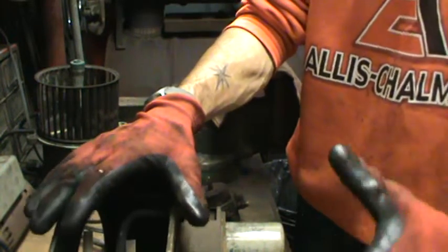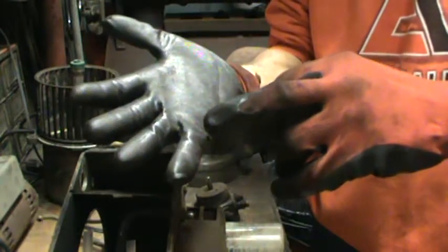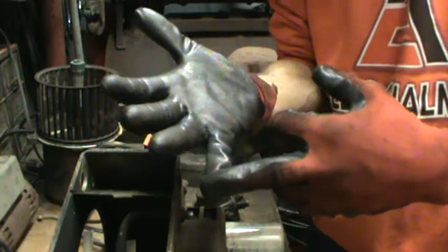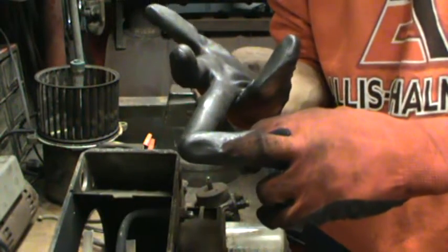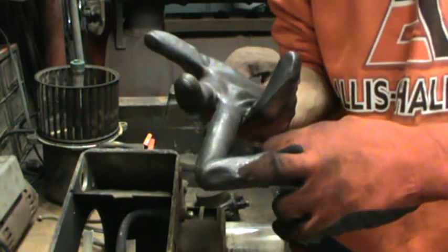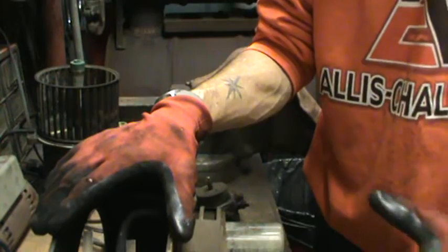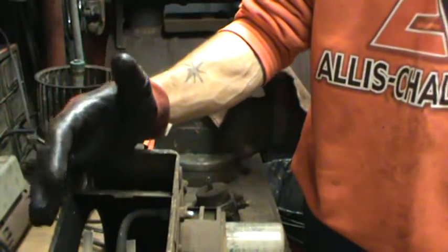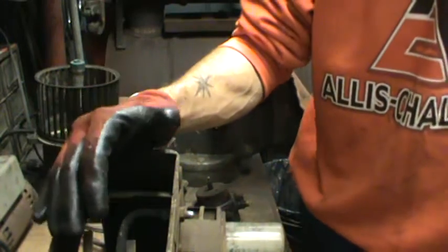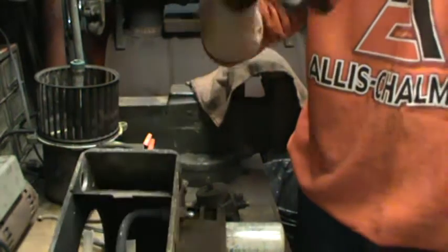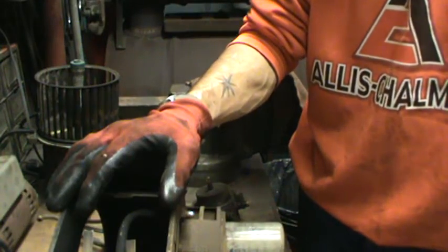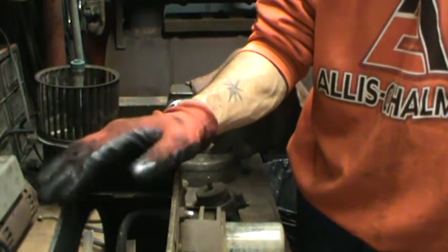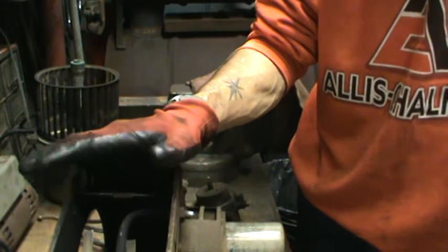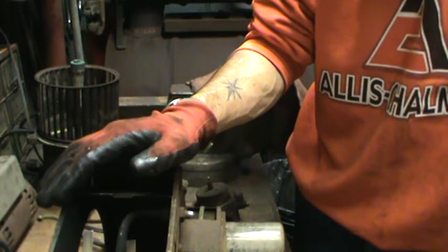and then swap your nozzles out to get an optimum burn with the optimum efficiency, 75-76% efficiency on the burn, with your best burn chamber temperatures, your least amount of lost CO or lost O2, your lowest O2 numbers, your lowest CO2 numbers, and no soot. I mean, there is a formula to getting it all right, but with these heaters here, these two that I've got, they're pretty much just like a boiler heater, an oil heater, or a house oil furnace.